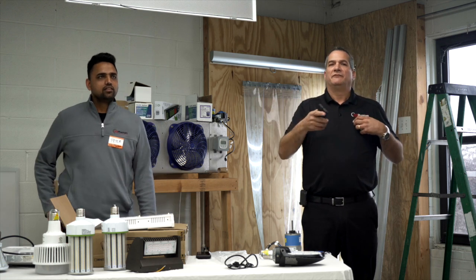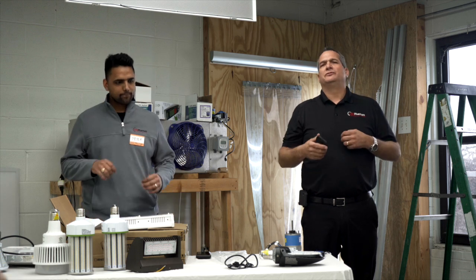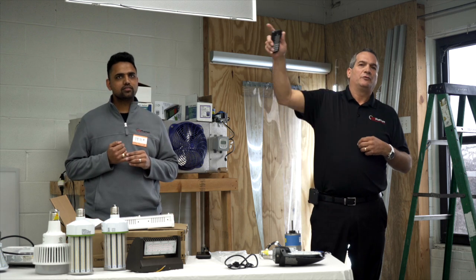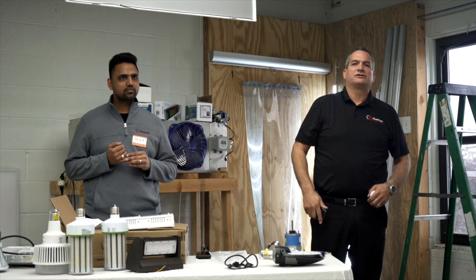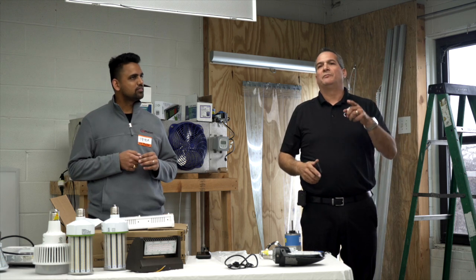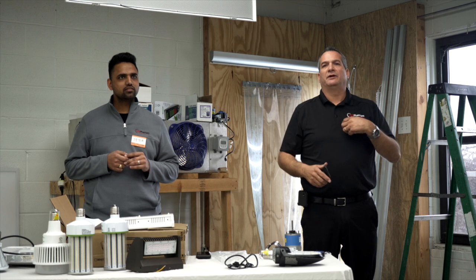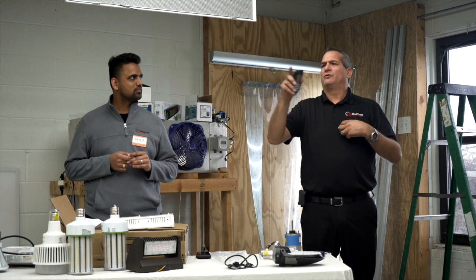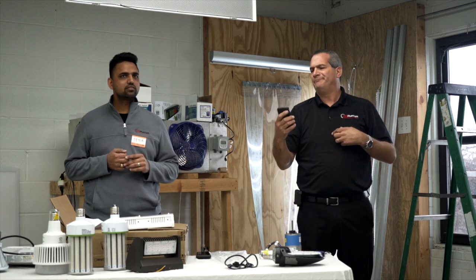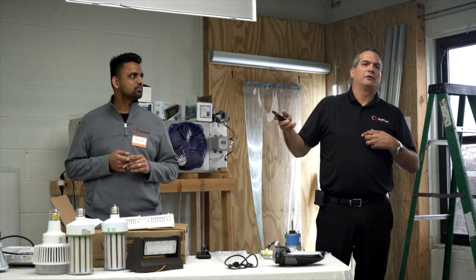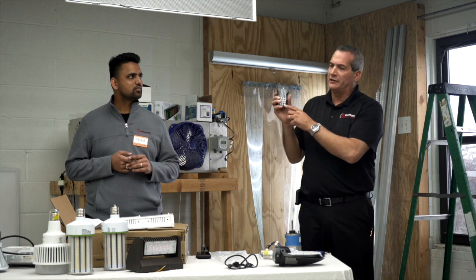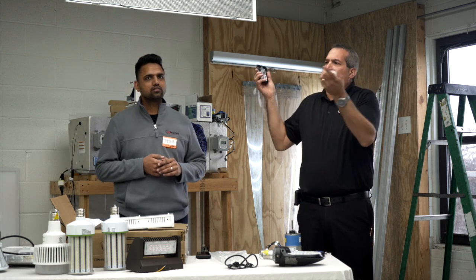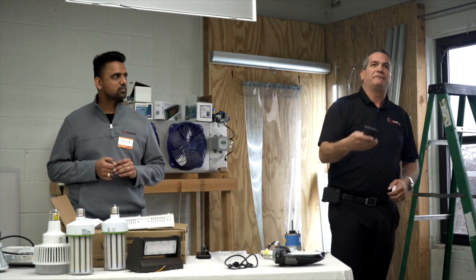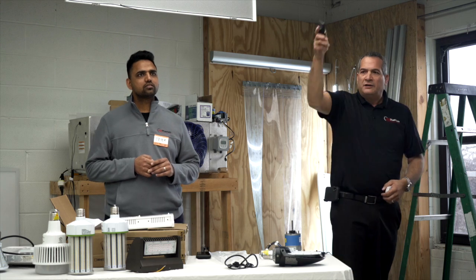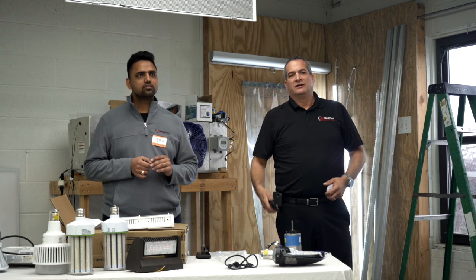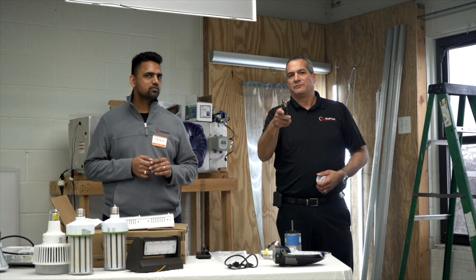Here's another solution. If any of you are electricians, if I told you I need an emergency light in row 2, row 4, and row 6, more than likely you're going to be pulling pipe and wire to accomplish that. With a system like this, I can go to any fixture in any row and say, you're now my emergency fixture, and program it as such. I could take that program and make it a macro in mode 4, mode 5, whatever mode I feel like putting it in. Just go up to that fixture, communicate with it, press the button. There's my emergency fixture. I didn't have to pull a bunch of pipe and wire to accomplish the same thing.